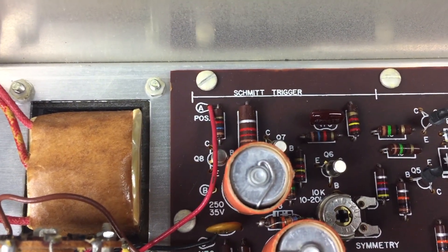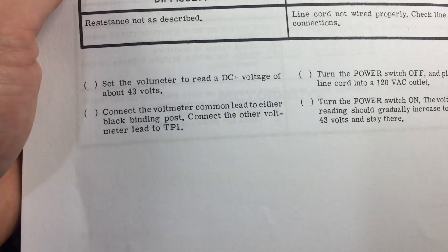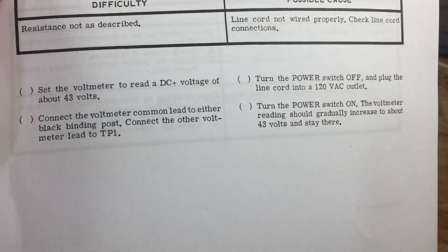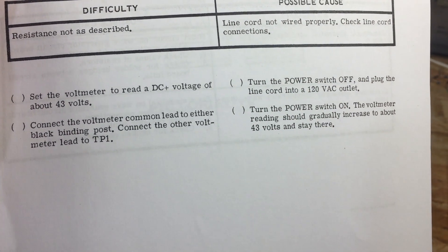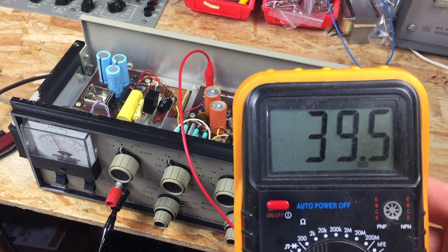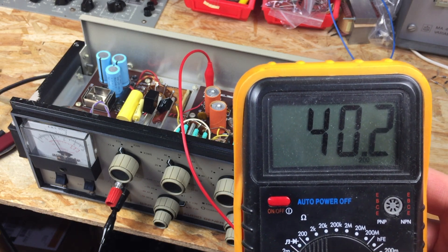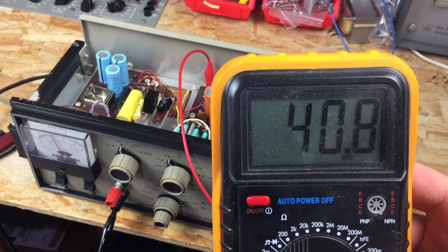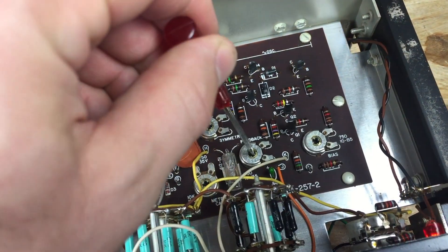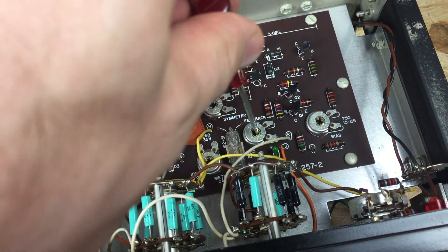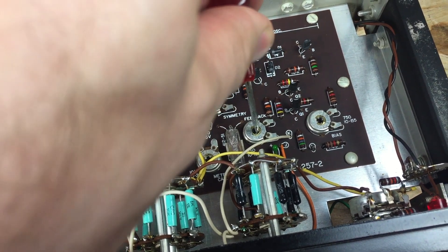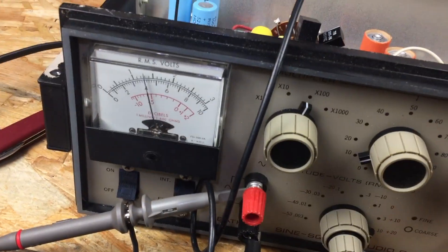I've started following the calibration instructions from the manual. The voltage at the test point is a bit on the low side, which is probably caused by old filter caps. The calibration parts all seem to be working fine and the meter responds well.